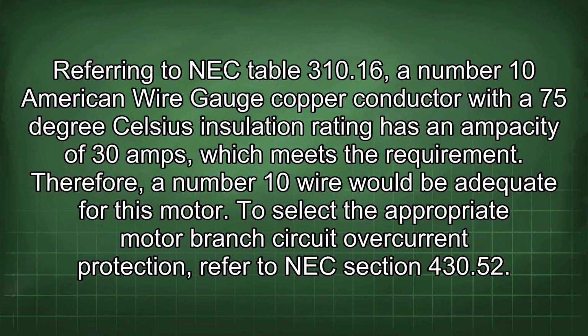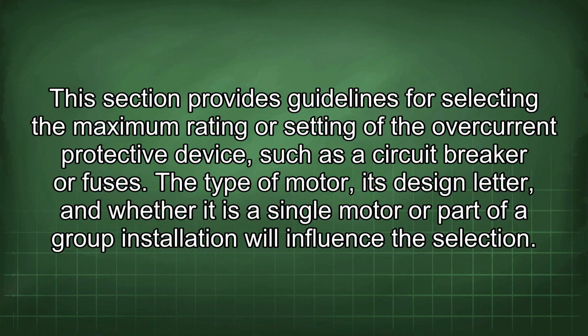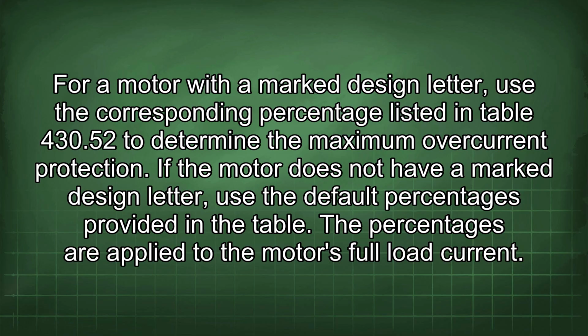To select the appropriate motor branch circuit overcurrent protection, refer to NEC section 430.52. This section provides guidelines for selecting the maximum rating or setting of the overcurrent protective device, such as a circuit breaker or fuses. The type of motor, its design letter, and whether it is a single motor or part of a group installation will influence the selection. For a motor with a marked design letter, use the corresponding percentage listed in Table 430.52 to determine the maximum overcurrent protection. If the motor does not have a marked design letter, use the default percentages provided in the table. The percentages are applied to the motor's full load current.